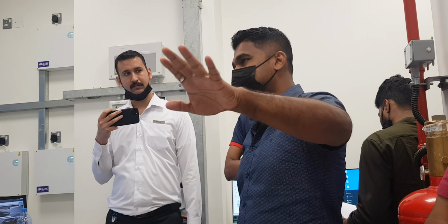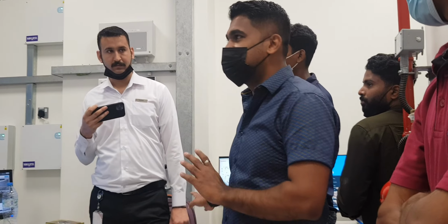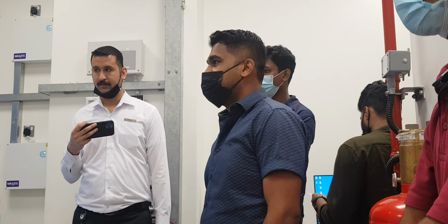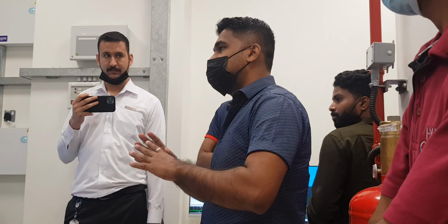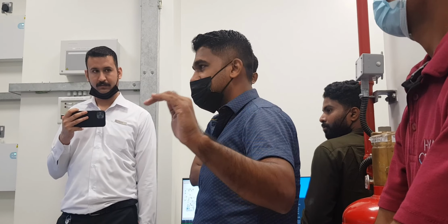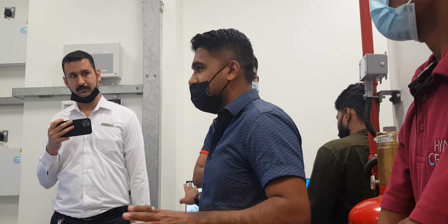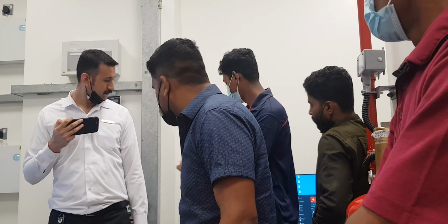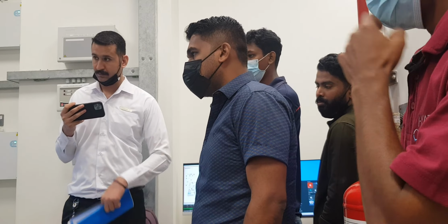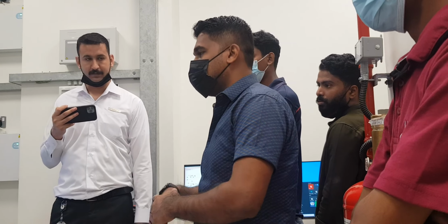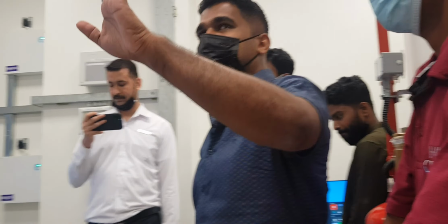Apart from these panels, we have the graphics control also, which one person has to be accessing 24/7. From graphics, you can do everything you can do at the main panel, except the acknowledging part, where there's a delay acknowledgement. Apart from that, disable, enable, resound, silence, everything can be done from graphics. Each and every device is placed as per the site condition and floor wise. Once you take the mouse to a device, you can see the location and everything.